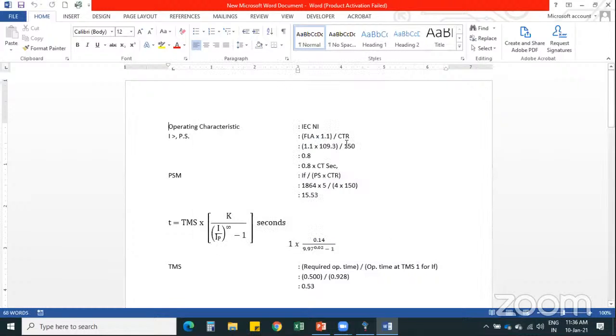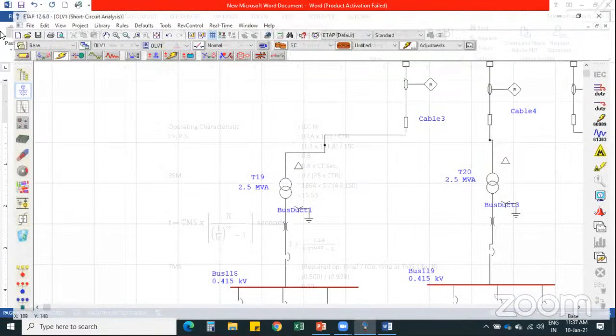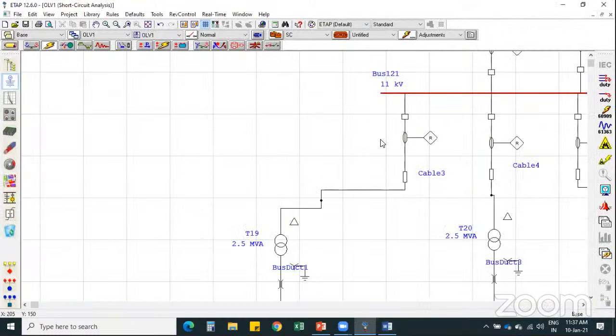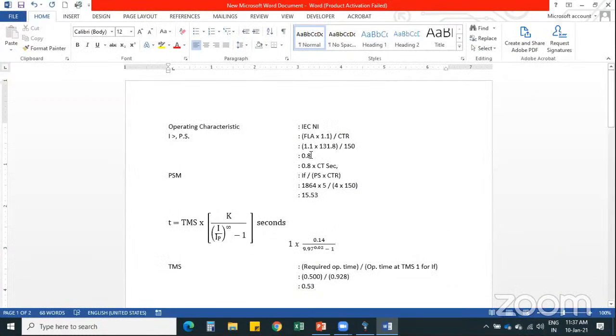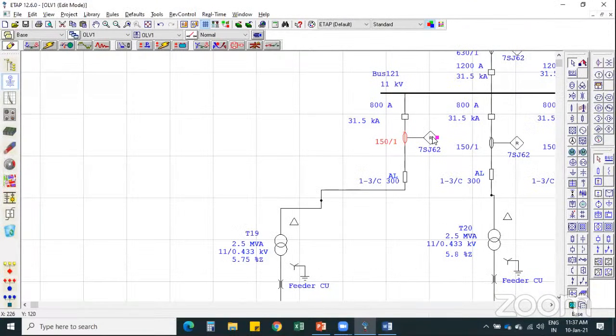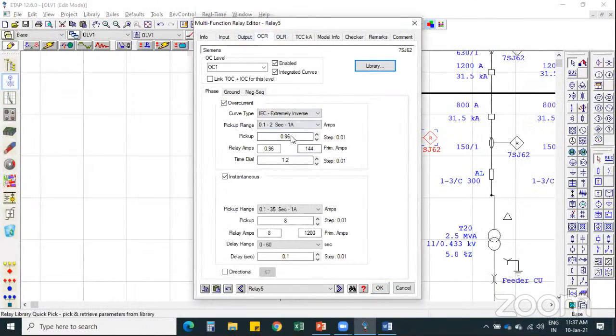Okay, is the screen visible to all? Yes, yes. So here we are taking the time grading margin of 10% for the HT section, and the CT ratio is 150/1. Now we will calculate 1.1 into 131.8. So it's 0.96. So the setting which we will give to this relay on the HT bus is 0.96.